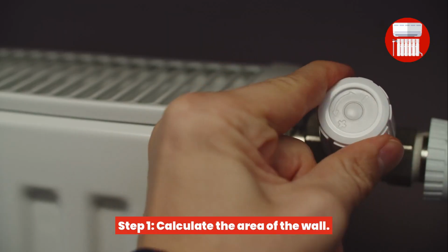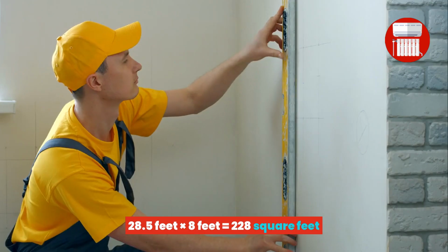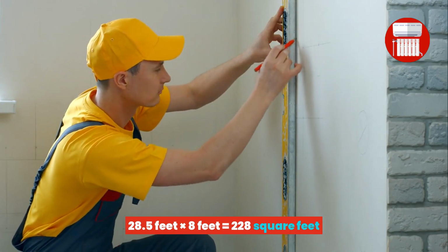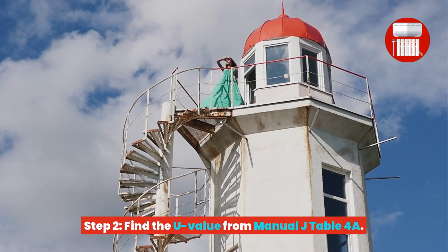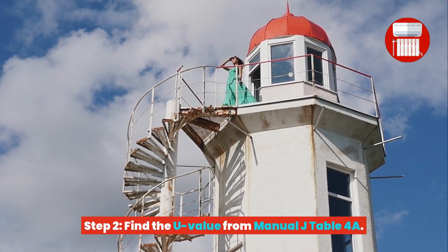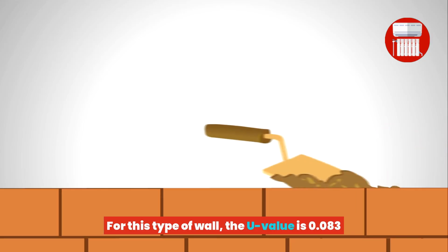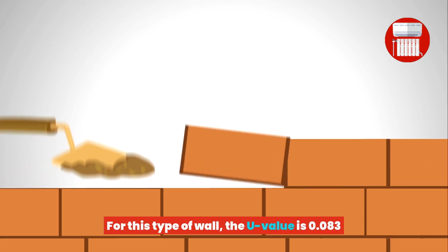Step 1, calculate the area of the wall. 28.5 feet x 8 feet equals 228 square feet. Step 2, find the U value from Manual J Table 4A. For this type of wall, the U value is 0.083.